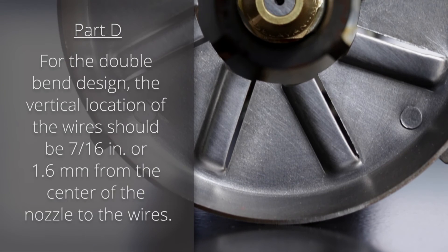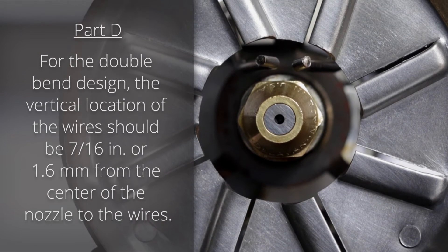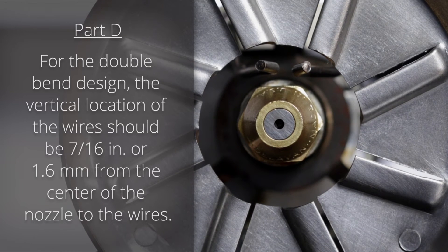Part D: For the double-bend design, the vertical location of the electrode wires should be 7/16th of an inch or 11 mm from the center of the nozzle to the wires.